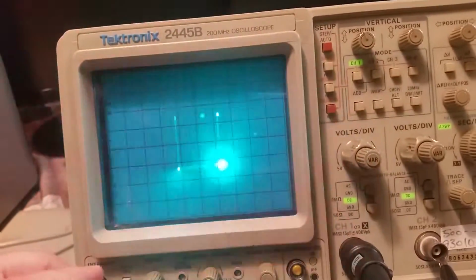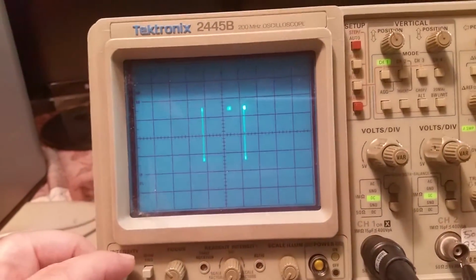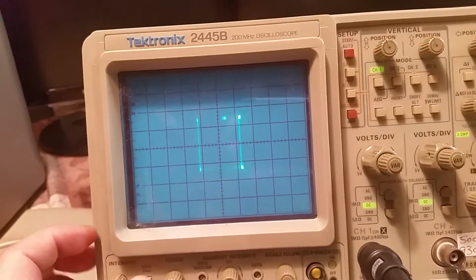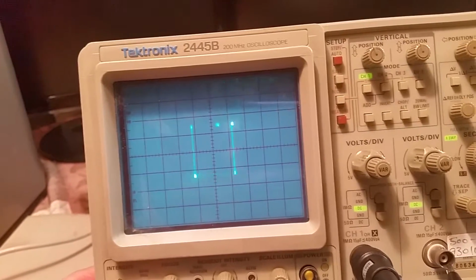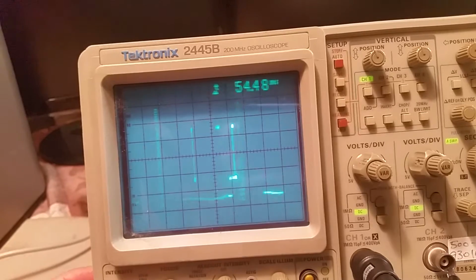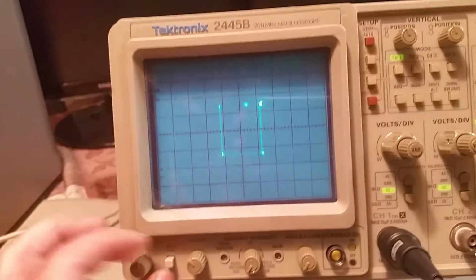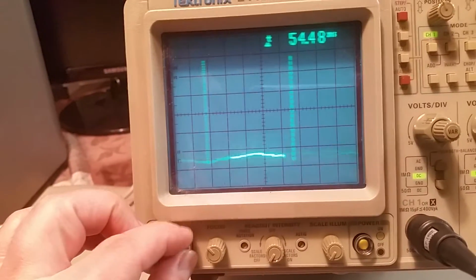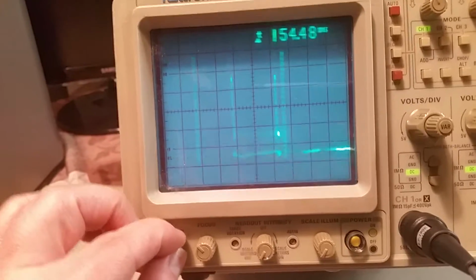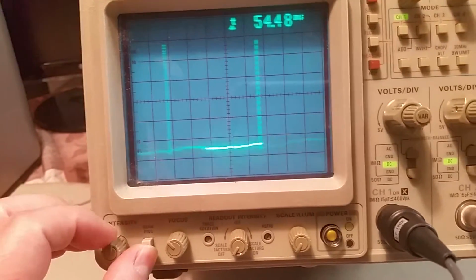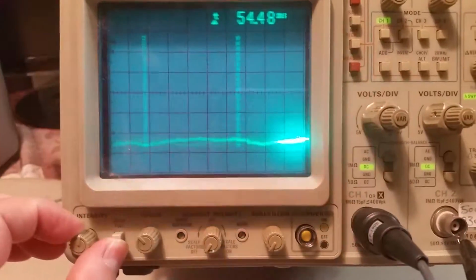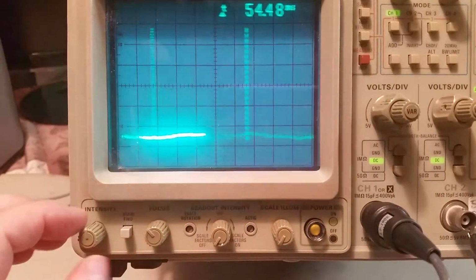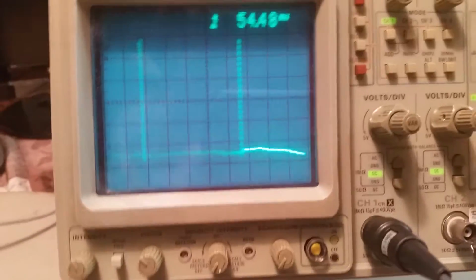Let me turn the intensities down. Here we go. Maybe they're drawing too much power. Okay, there we go. We have something. It's like the beam finder was stuck. There it goes. Well, it tried to come back out. Oh, there it is. Okay, so I think we got an intermittent switch here. More than likely what's going on, this thing had sat up so long that it's got some corrosion built up in it.